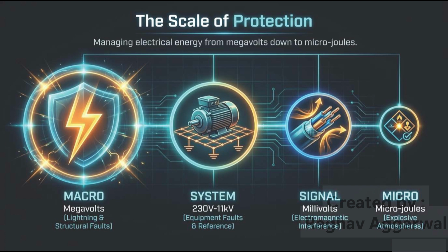Moving smaller, we reach the signal level, where many instruments operate using millivolt signals. These signals can easily be disrupted by electromagnetic interference, often called EMI. Finally, at the micro level, we deal with tiny amounts of energy measured in microjoules. Even these very small energy levels can become dangerous if they create a spark inside an explosive atmosphere.